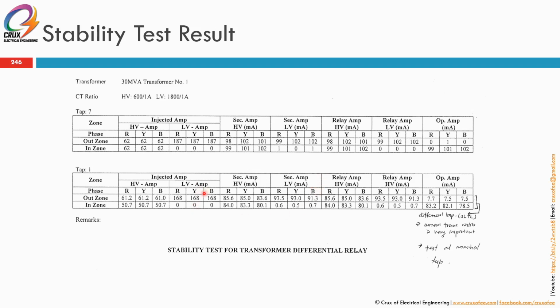So this is a typical stability test result, as you can see here. You have your relay amp, HV, LV. For outzone, you want to make sure that the operating current is almost zero. So this is outzone. They are simulating outzone primary injection. The primary side is seeing 100 milliamps, the secondary side is also seeing 100 milliamps. This is in terms of secondary. So there's no differential current. That's why it's almost zero, 0.01 amp.